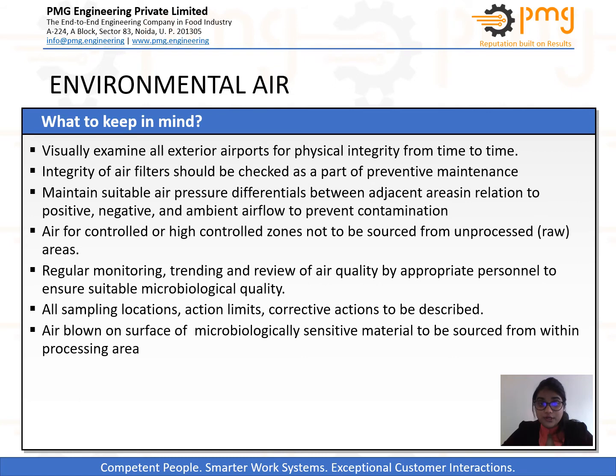Number three: air sourced from outside to be filtered to the level required for the product. Air blown on the surface of microbiologically sensitive material to be sourced from within the processing area. Air for control or high control zones not to be sourced from unprocessed areas. Air supply to the filter in an aseptic filling system to be filtered through HEPA filters, known as H13 filters.